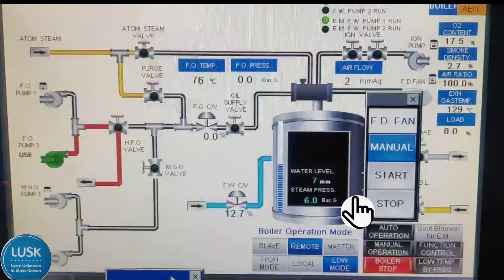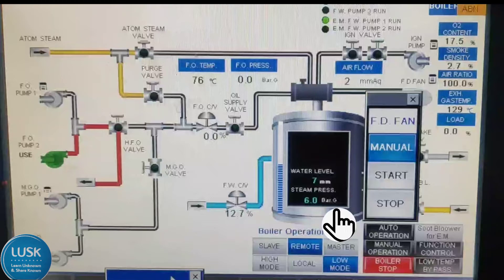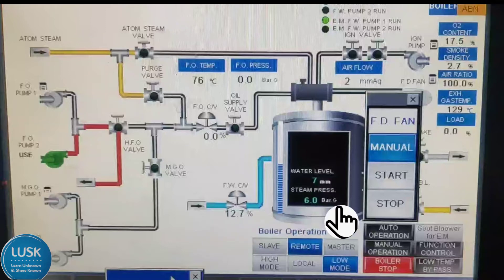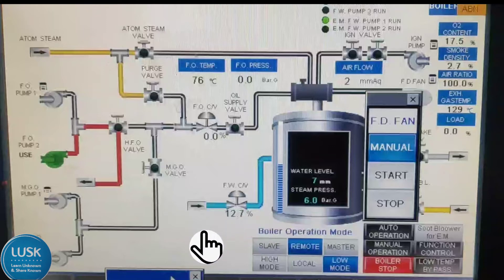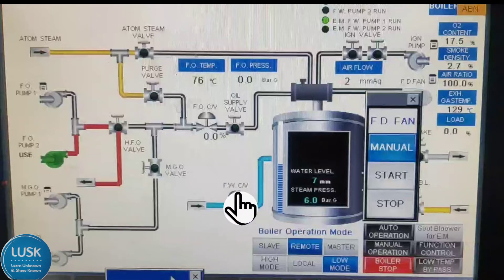0mm is the normal level. If it goes plus 100mm, 150mm, or 200mm, it is high water level. And vice versa — if it goes to minus 50, minus 100, minus 200, that is low water level. There is one valve here: the feed water control valve, which controls the water level in the boiler. If we set the set point at 10mm or 20mm or 0mm, this valve will make sure that water level does not go beyond the set point.